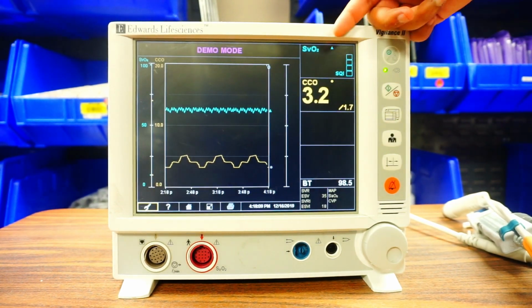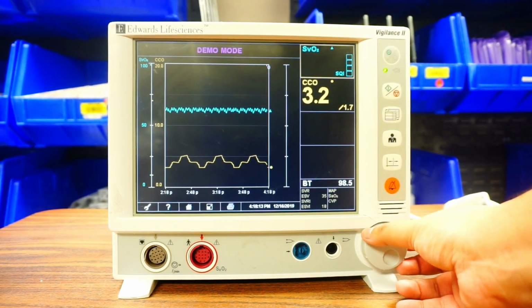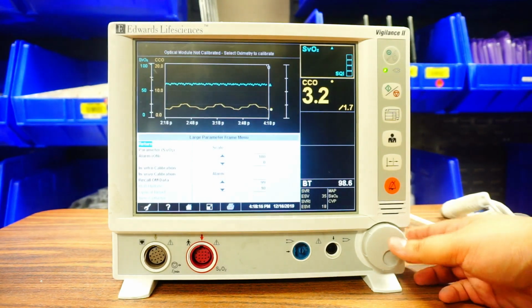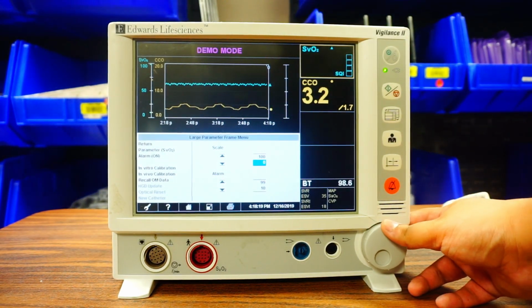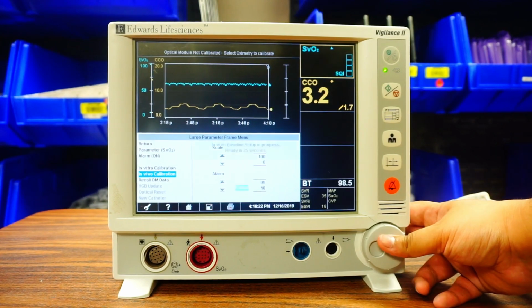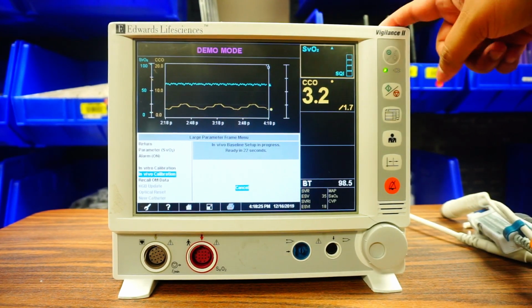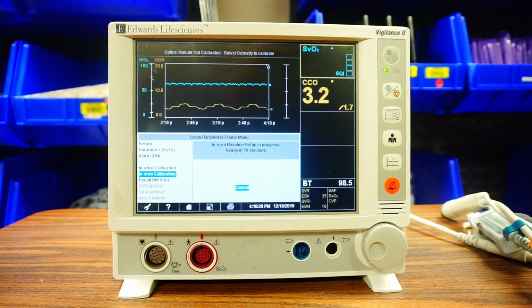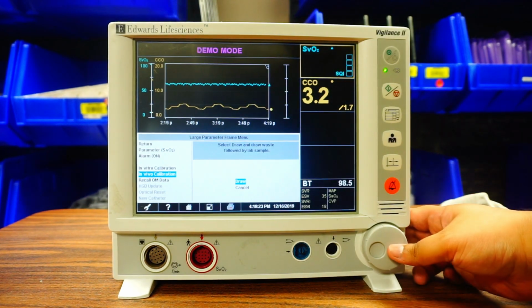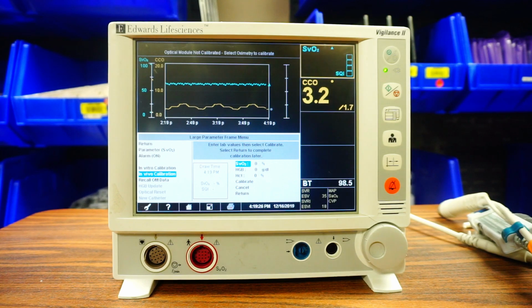So now I'm going to be showing you how to get your SVO2. So what you're going to do is you're going to toggle over to where your SVO2 is. I'm going to go ahead and click that. And then I'm going to go down to in vivo calibration, and I'm going to click it. Again, it's going to do a baseline setup for 25 seconds. At this point, I'm going to get my VBG syringe from my RT. They're going to be ready to get my VBG. I'm going to be drawing this from my yellow port on my Swan. I'm going to give them the blood, and the next screen is going to be that I drew the blood. I'm going to go ahead and press draw now. And once I get my results, I'm going to go ahead and put them in.